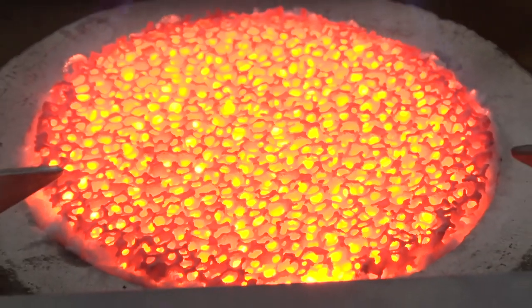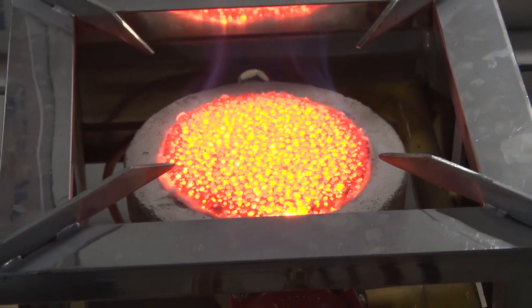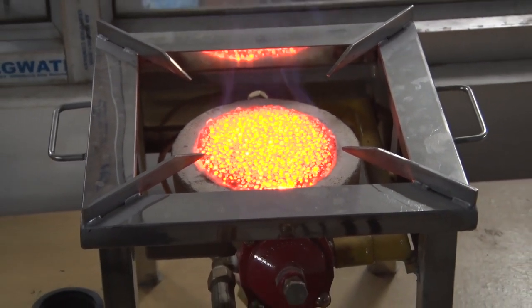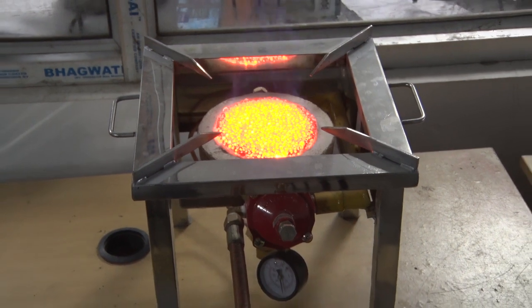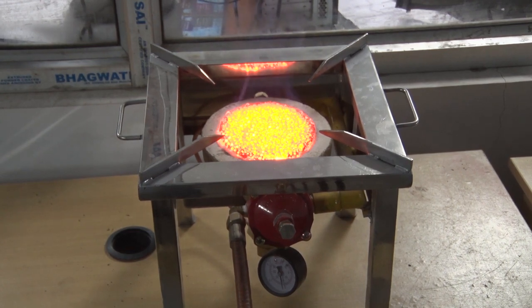For industrial applications including space heating, ceramic dryers, and food dryers, we are currently exploring. Now you are seeing the combustion of the newly developed porous radiant burner of about 5 to 7 kilowatt capacity. The burner is completely in flameless mode — you cannot see any flame. This burner can provide fuel saving of about 40 to 50 percent and also provides about 85 percent reduction in CO and NOx emissions. We have also done the kitchen performance test at actual conditions and obtained about 30 percent saving in cooking time.